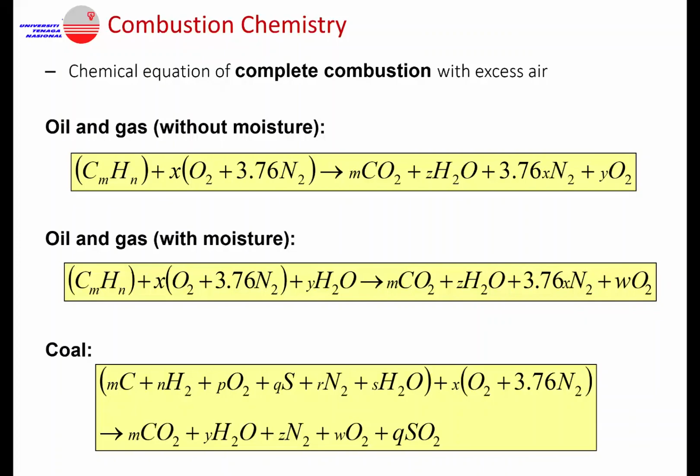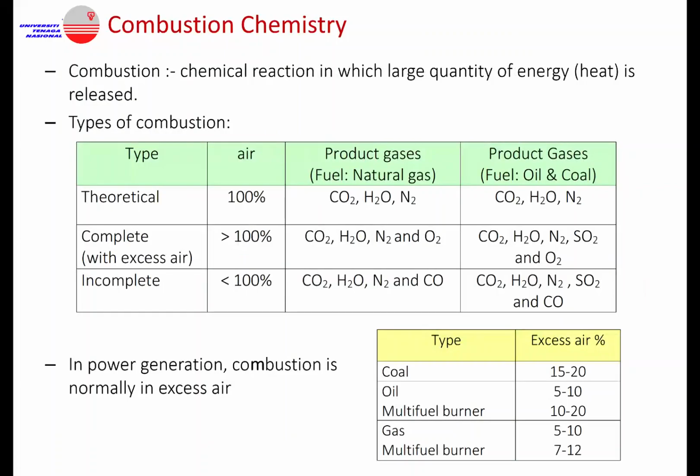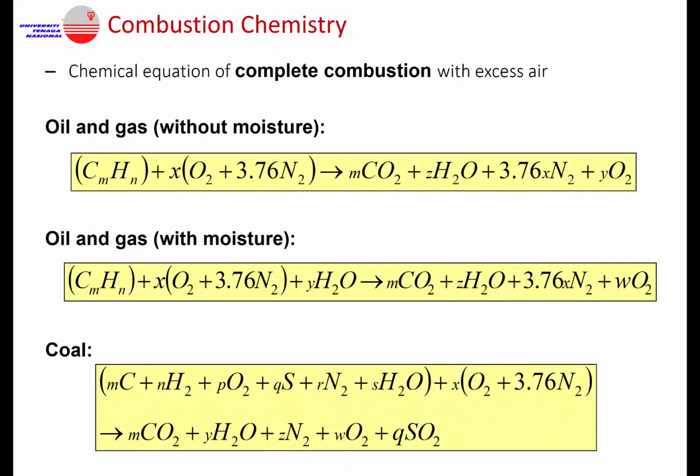You supply excess air, of course you ensure combustion is complete, but at the same time you are also losing heat. All the additional air is used to absorb the heat produced after combustion. So the amount of air you supply has to be just right to ensure complete combustion. Not too much, not too little.